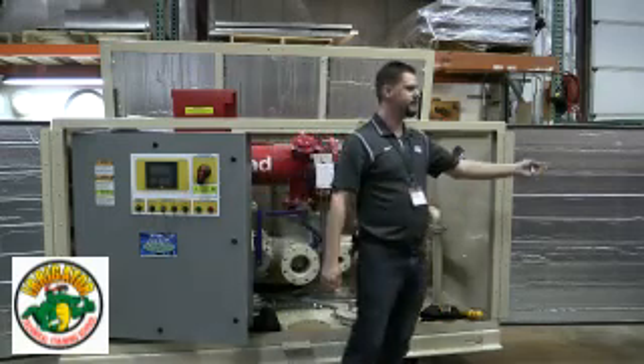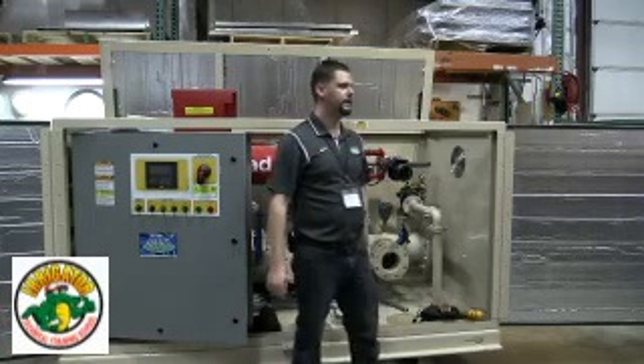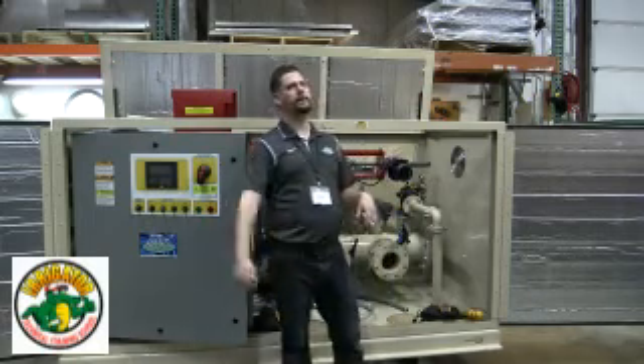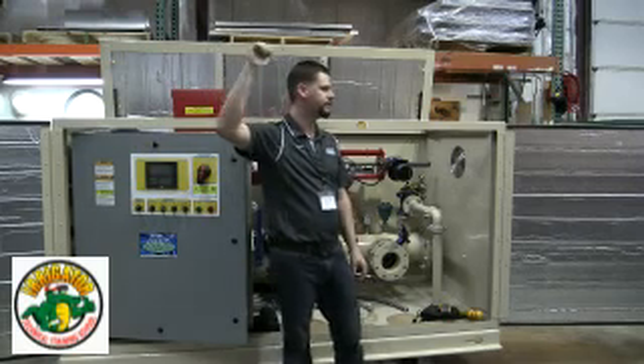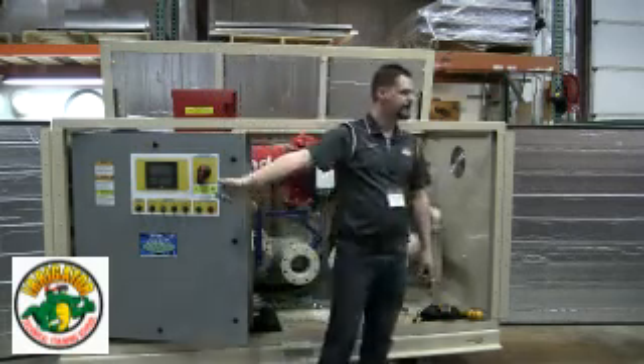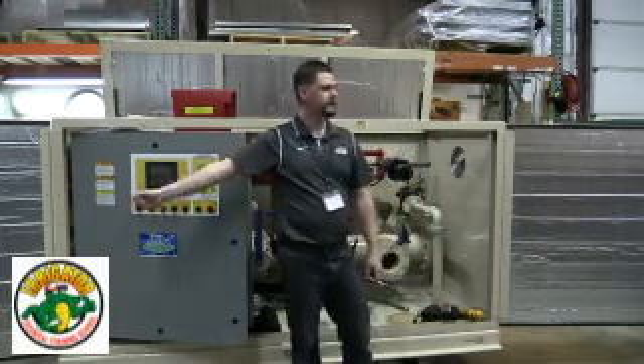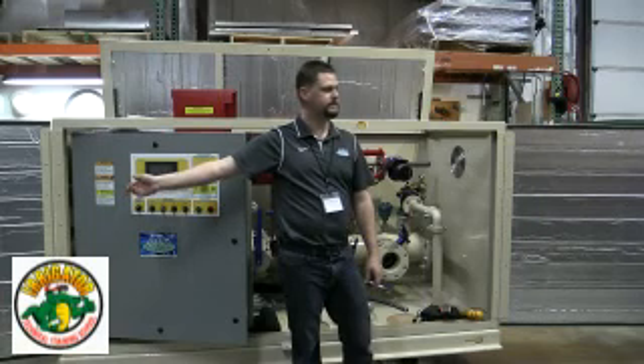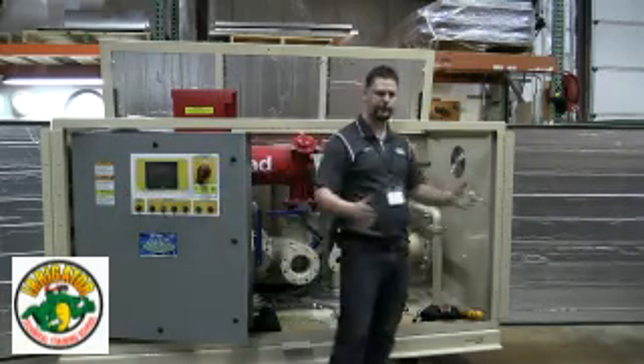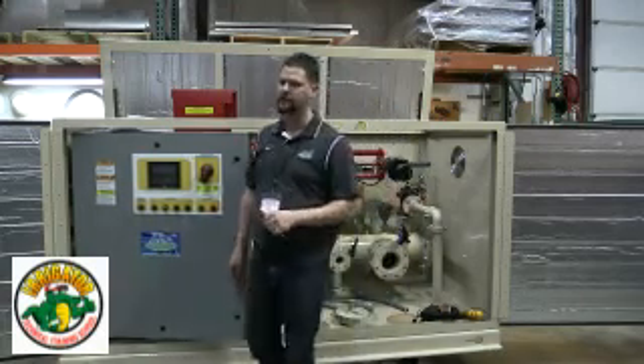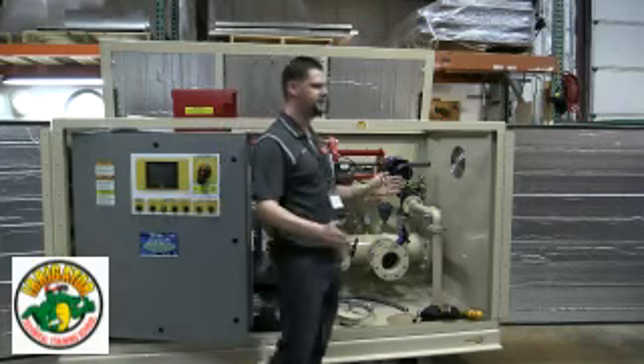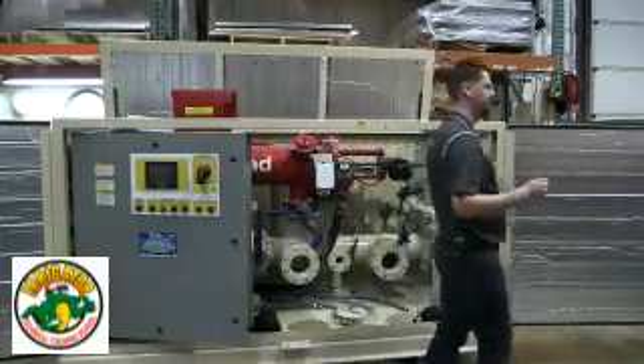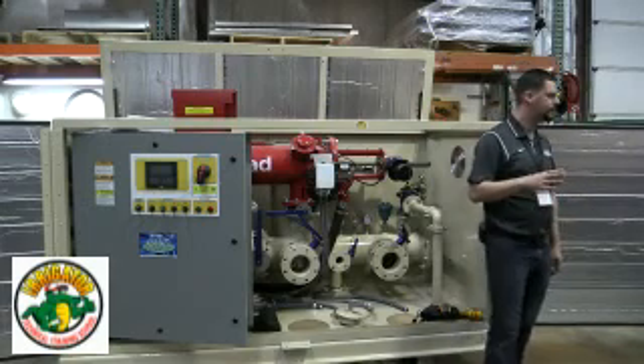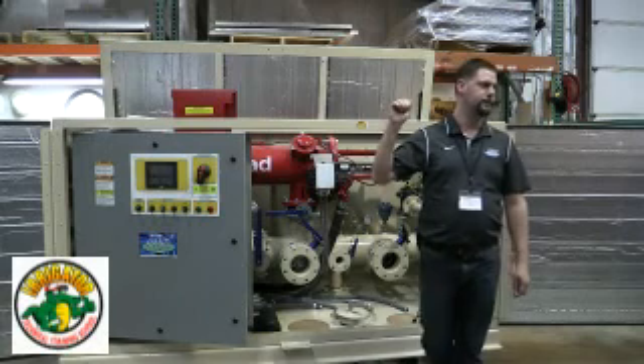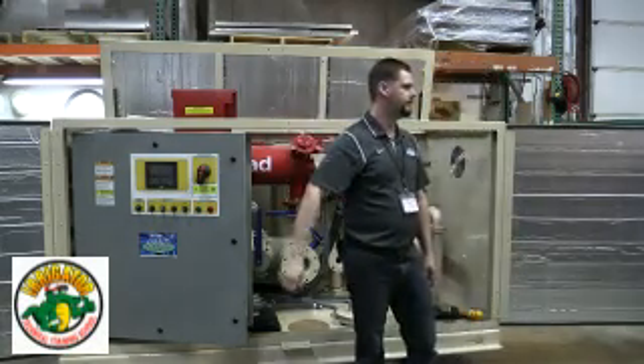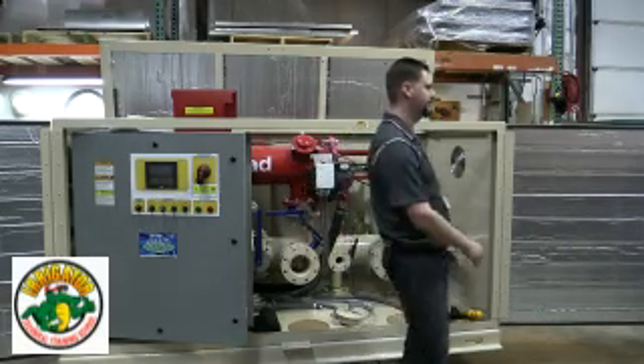What'll be happening is you'll see oscillations in pressure, back and forth and up and down. And you want that to be at as low of a pressure as possible while the air is expelling out of the air release or out of an open zone. And I will continue step 1 through whatever. Slowly fill it up, get to 10 pounds, turn it off. As soon as it stops this back and forth business that we get when we have a pipe full of air, I'll get it up to 20 or 25 pounds, turn it off as long as it's not still jumping all over the place. Back on. Once we get above 40, in the 50 range, I'll put it in auto, let it come to pressure, fall asleep, and then I'll shut their isolation valve. Now we're testing the pump station.